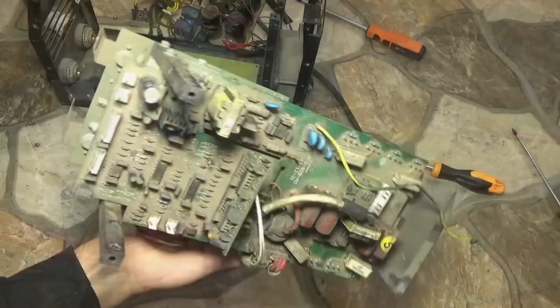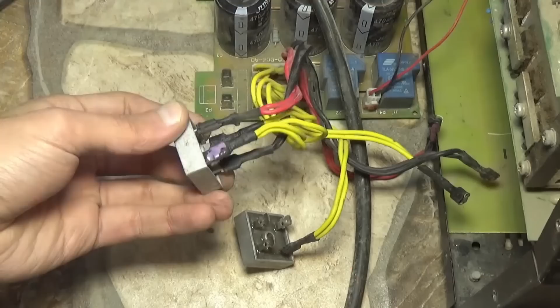On the positive side, the inverter is bridge type with good, competent control, a well-thought-out cooling system based on the tunnel principle, massive heat sinks, and a solid transformer wound with Litz wire. The input section is also quite good. They didn't skimp on capacitors, bridges, and relays. In similar devices, they usually put in one relay, one bridge, and at best 4 capacitors of 470 microfarads, but here there are as many as 6.